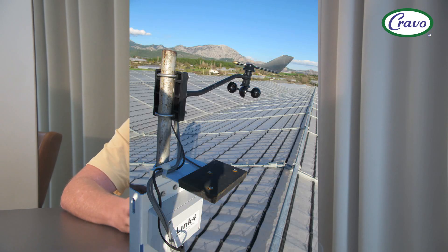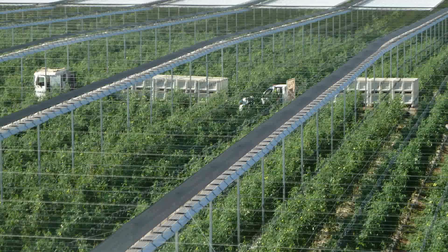That will help protect the plants from risk of hail damage. But the primary sensor we're using is a black plate temperature sensor that measures how much heat is available outside, factoring in the air temperature but also the heating effect of the sun. If this black plate goes below 12 degrees, outside is becoming too cold and we close the roof. If the black plate temperature goes above 15 degrees, the roof will retract 100% and the plants are now outside getting full sunlight.